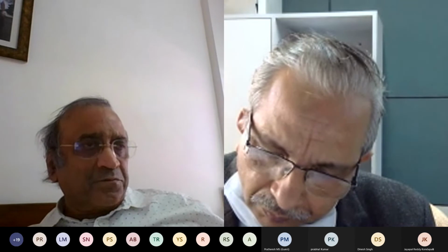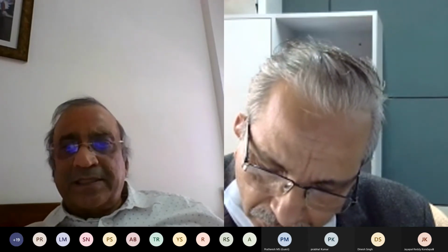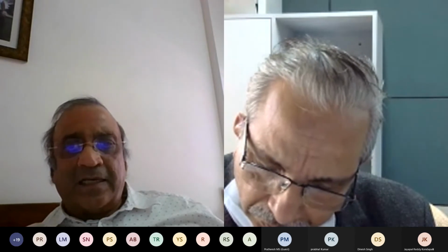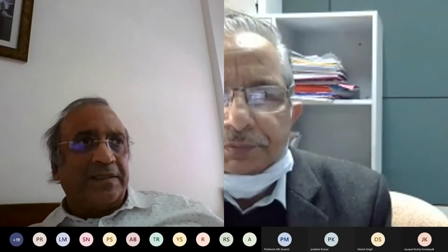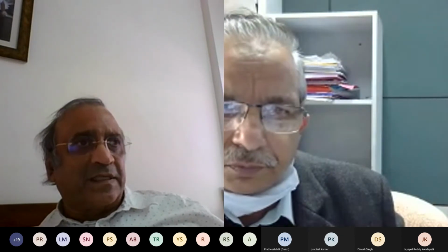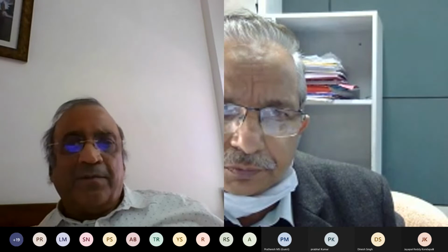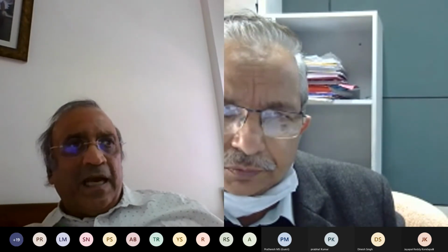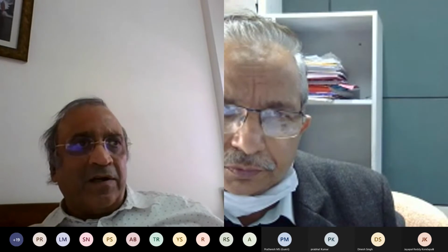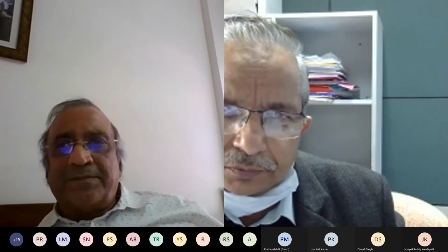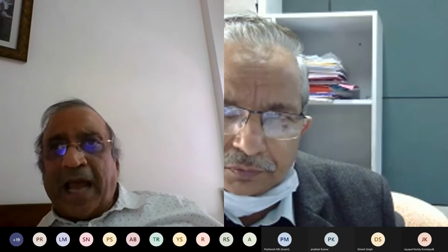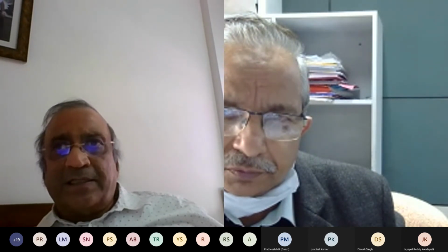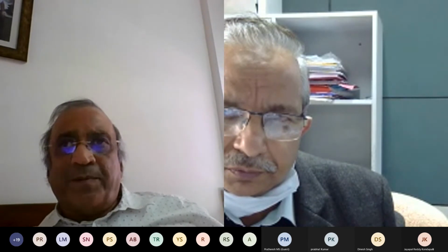And of course, it is not unilaterally decided by the load dispatch center. In the regional power committee, normally there will be a discussion on all aspects of black start, and after all the requirements are met, they can declare that this is the power station which will take startup power from this particular hydropower station, and this is the corridor which will be required on a dedicated basis. When we say dedicated basis, it means there should not be any other hanging load of a critical nature on that corridor. So you should be able to line up that corridor and do the line charging.